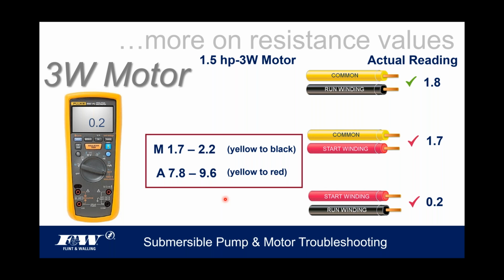In this slide, the bottom two failed. The yellow and red failed, and the red and black. I told you every time one of the above fails, that one always fails. But look at the commonality between the red check marks. Yellow and black are fine if they're together. It's only when we add the red wire to them that they fail. And so more than likely, that short will be in the start winding, the red wire. More than likely.